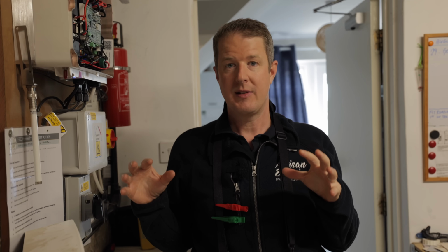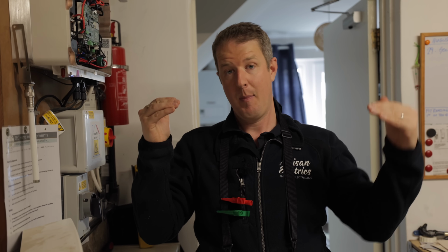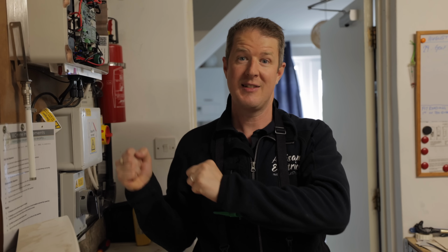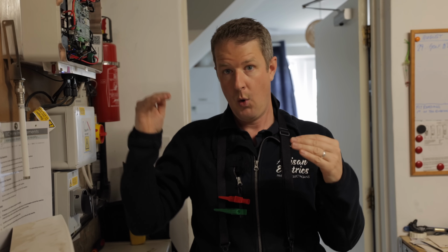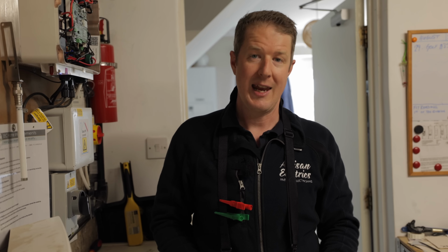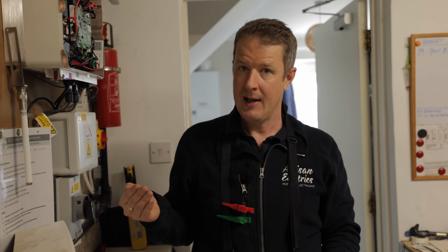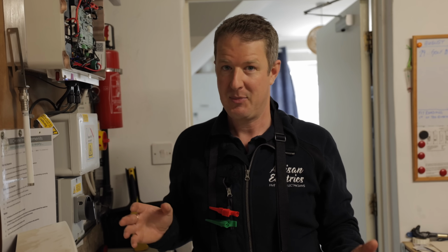How solar works is that the inverter has to push out a higher voltage of AC than the base on the grid, so that the house uses the solar voltage first rather than pulling power from the grid. So to have solar, you're always going to have a slightly higher voltage than a normal base voltage anyway. If it was over 253 volts, I would be worried, and then we could do something, but currently as it stands, it's absolutely fine.